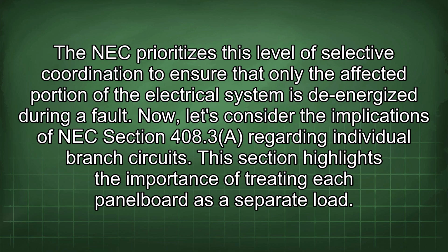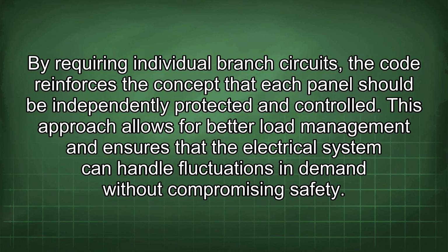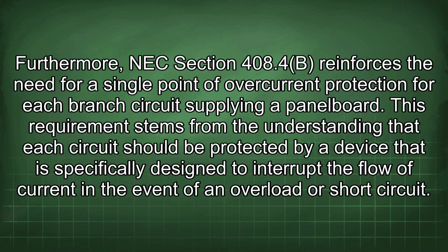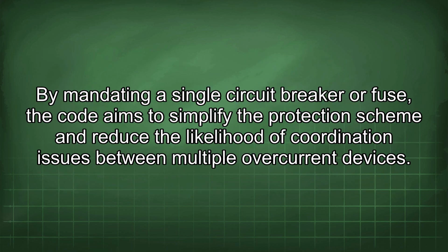This section highlights the importance of treating each panel board as a separate load. By requiring individual branch circuits, the code reinforces the concept that each panel should be independently protected and controlled. This approach allows for better load management and ensures that the electrical system can handle fluctuations in demand without compromising safety. Furthermore, NEC Section 408.4(B) reinforces the need for a single point of overcurrent protection for each branch circuit supplying a panel board. This requirement stems from the understanding that each circuit should be protected by a device that is specifically designed to interrupt the flow of current in the event of an overload or short circuit. By mandating a single circuit breaker or fuse, the code aims to simplify the protection scheme and reduce the likelihood of coordination issues between multiple overcurrent devices.